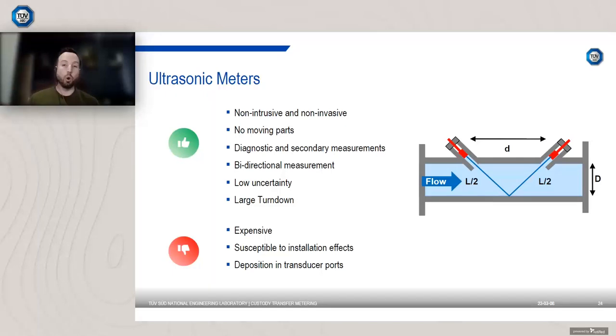So again, for these to work optimally, they require nice, fully developed flow, although some multi-path devices can now compensate for distortion in the flow stream. And in the transducer ports, you can get deposition that can affect their ability to send and receive the ultrasound. But they are quite flexible, and they're available in quite small and quite large pipe diameters. So you can get up to 48-inch size ultrasonic meters, right down to very small bore as well.